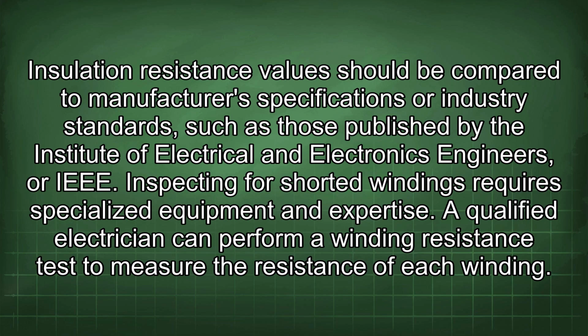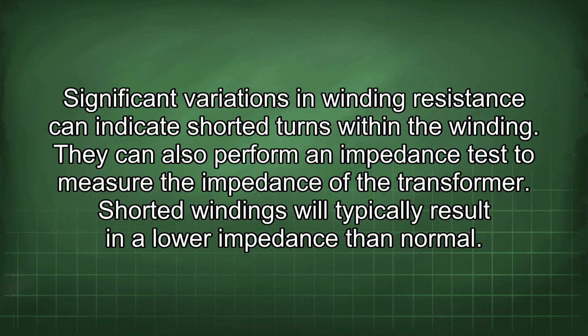Inspecting for shorted windings requires specialized equipment and expertise. A qualified electrician can perform a winding resistance test to measure the resistance of each winding. Significant variations in winding resistance can indicate shorted turns within the winding. They can also perform an impedance test to measure the impedance of the transformer. Shorted windings will typically result in a lower impedance than normal.